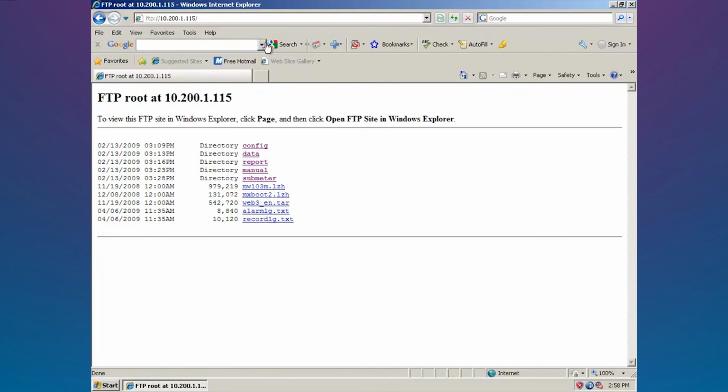The MW100 can also be used to take manual samples and generate reports. As you've seen, it can do custom web pages. It comes in a Class 1 Div 2 variant for some explosive environments. And the MW100 also supports steam, saturated and superheated, and natural gas calculations like AGA 3 and 8.